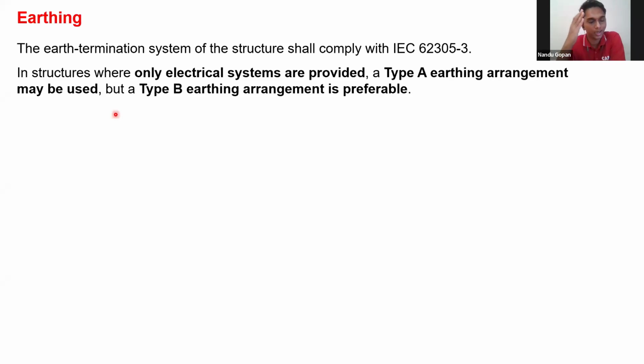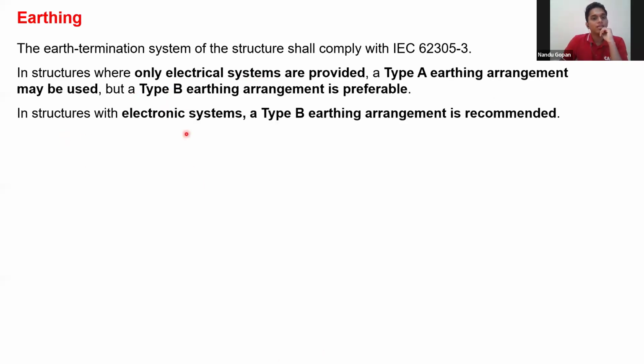Earth termination and earthing should be as per 62305 part 3. In a structure, earthing is divided into two types, type A and type B. If you have a simple house, you can use type A earthing, but the standard recommends type B earthing. If you have a structure with electronic systems, the standard recommends type B earthing - they are not even considering type A, only type B.